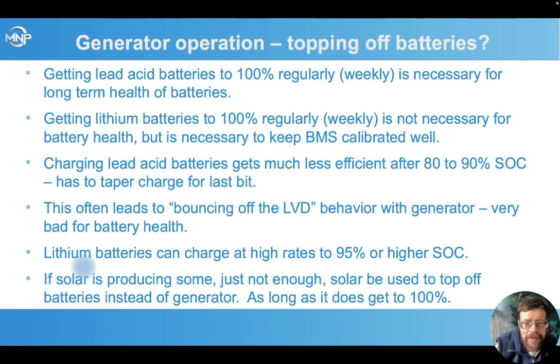Another question that this brings up is, how often do we need to get the batteries full? With lead acid batteries, we needed to get them full regularly, weekly to every 2 weeks, just for the long-term health of the batteries, to keep them from sulfating. Lithium batteries, they don't care for battery health about getting to 100% regularly, but you do need to get there regularly, once a week or every 2 weeks, just to keep the battery management system, which is reporting your state of charge, keep that calibrated well.